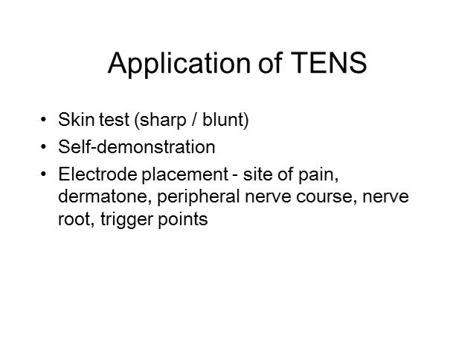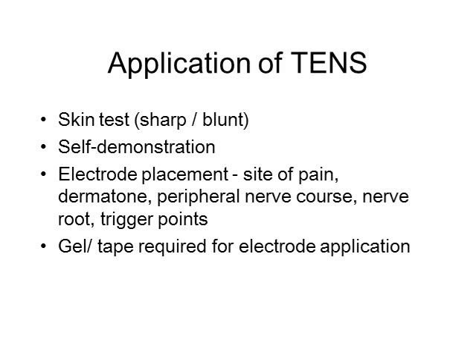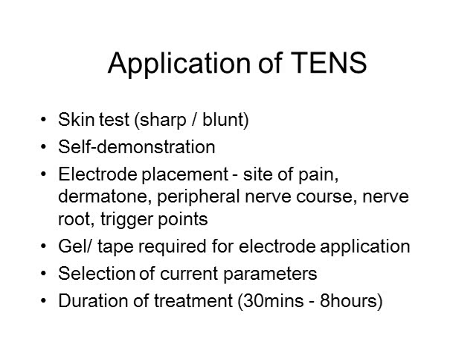An even distribution of gel is required on each electrode. This ensures an even current density and improves patient comfort. Tape should be used to hold the electrodes in place, applied so that even pressure is obtained on each electrode. You should select the appropriate TENS parameters depending upon the desired effects and patient comfort. The duration of treatment should start off low, perhaps half an hour, and should be increased if there is no effect or if longer pain relief is required. If TENS is used for long periods, drying out of the gel may become a problem, so the patient should be encouraged to remove the electrodes, clean them, and reapply with new gel from time to time.